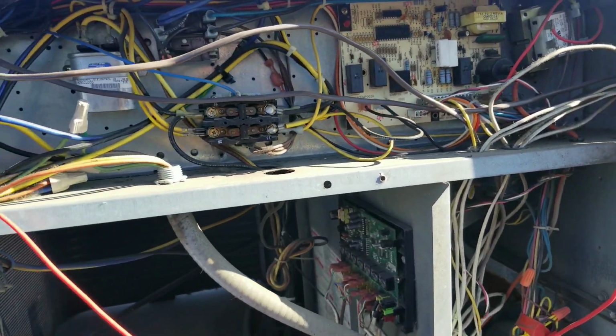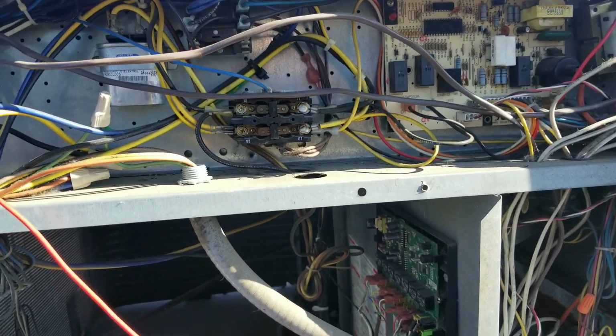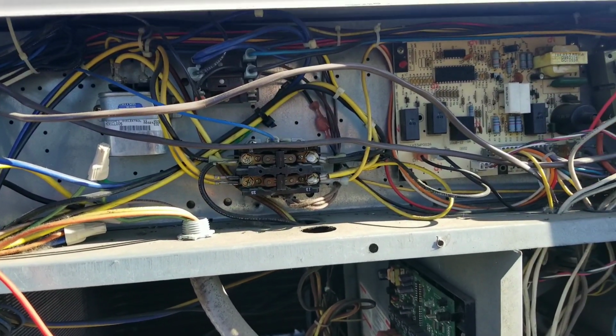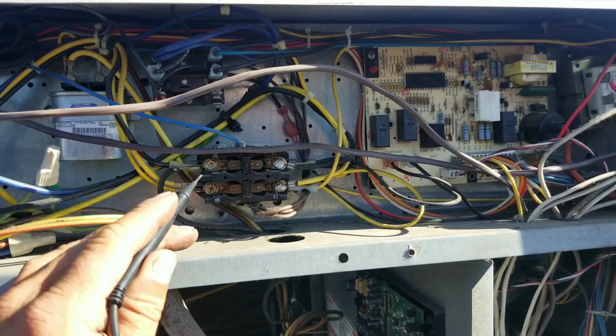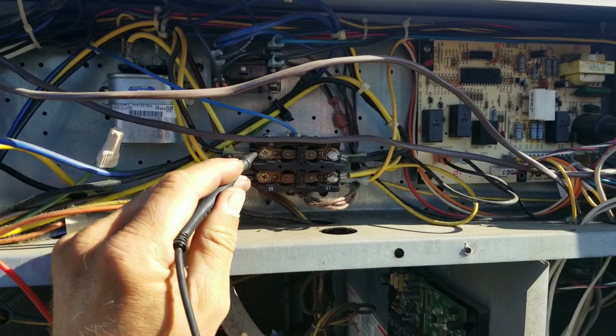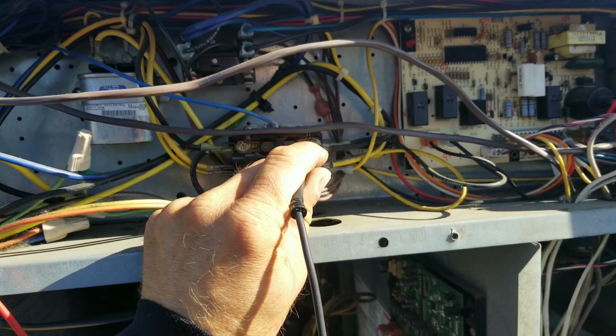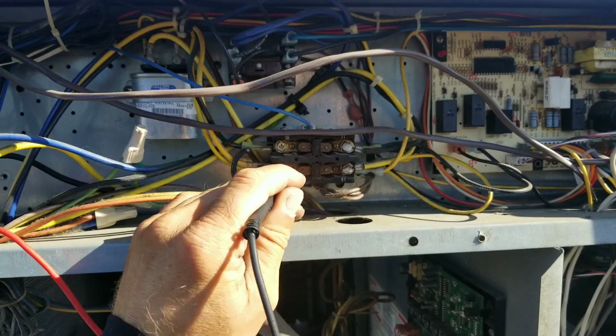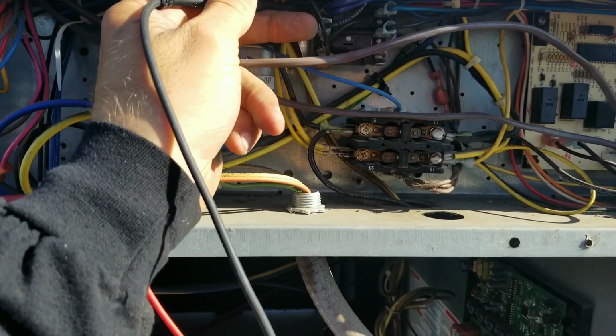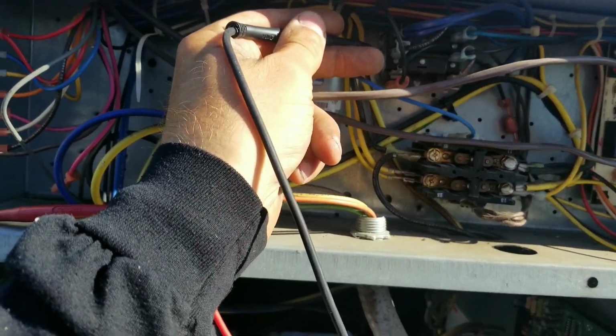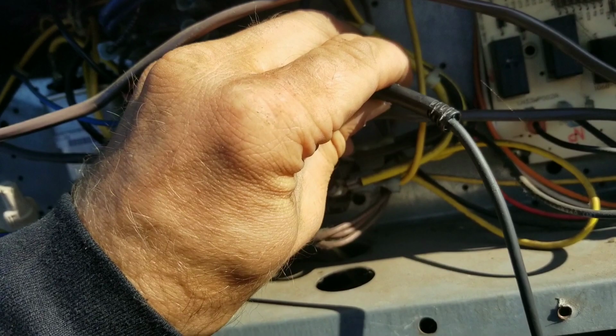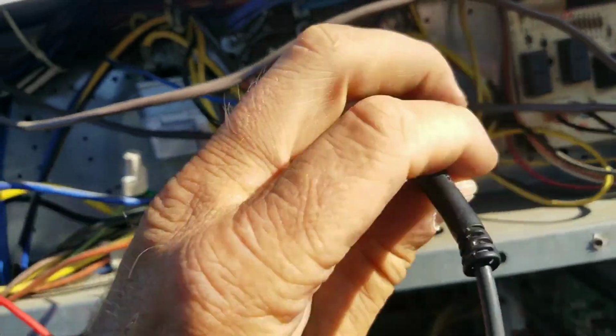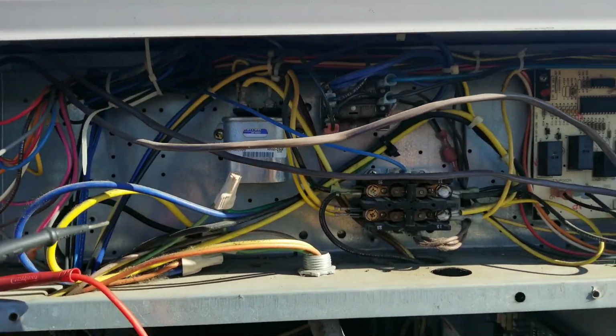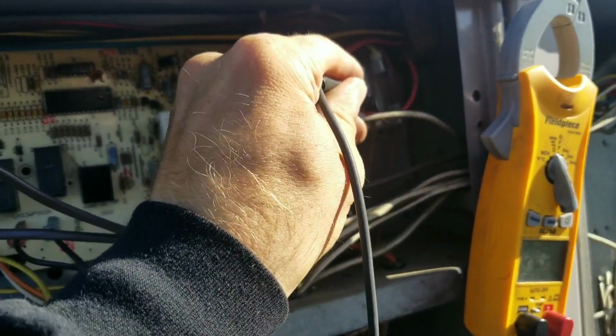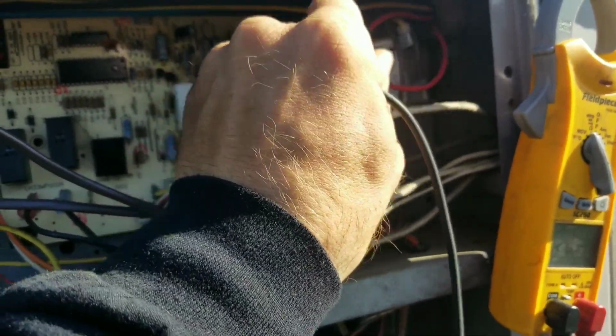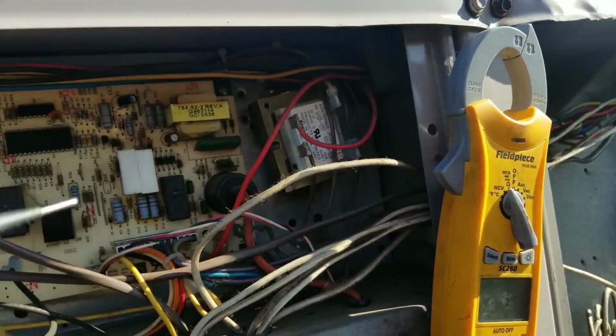Alright, I got my meter all set up. One lead is attached to the ground, and with my other lead I'm just going to check the various components to ground and see if we have any continuity anywhere. I'm just doing it at the controls first, and then I'll go to each individual component and I'll check those to ground as well. So far, nothing on my contactor. My switching relay, nothing right there. Nothing. Nothing. Capacitor, nothing. Let's check our transformer. Nothing. Nothing. Check the chassis. We're still grounded.